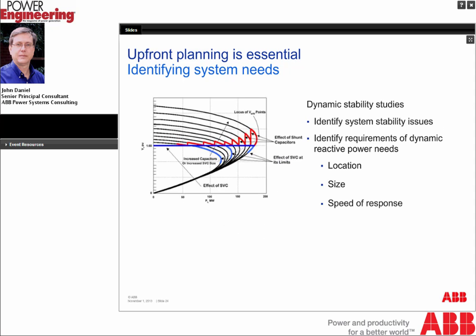You also need to be concerned with the dynamic stability. There are a number of dynamic reactive devices that Eric John will be talking about here shortly that can be placed out there, and it's important to know where they should be, what kind of device might work well, the size of the device, and how fast you need it to respond to help keep the system up and operating well.